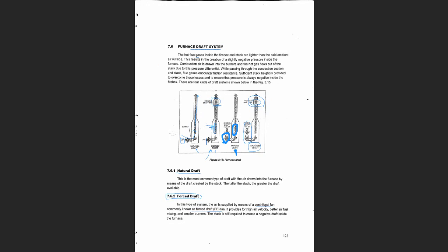وفي الأسفل اير ريجسترز على كل بيرنر، طبعا هي صعبة شوي. هذه في الأفران. جميل. بينما في البويلرز أشهر نوع عندك اللي هو هذا الفورس درافت، إنه يكون عندك كومبريسور compresses the air to flow into the firebox of the boiler. جميل. ففي الأفران عادة induced draft، بينما البويلرز يكون forced draft. جميل. طبعا في الأخير عندنا هنا هذه الصفحة الأخيرة جالس يتكلم عن البالانس درافت.